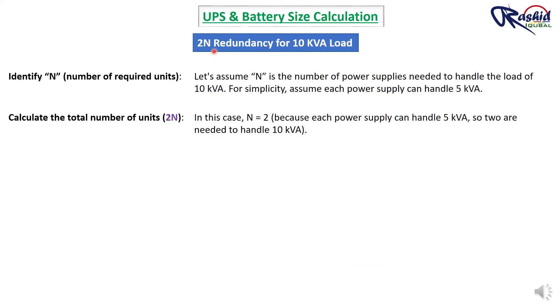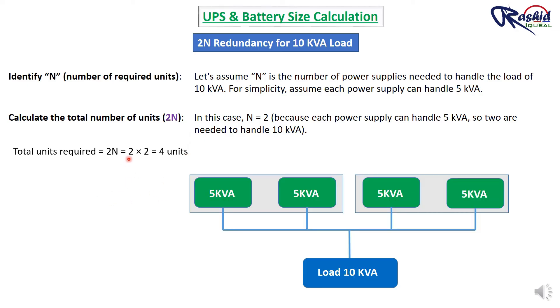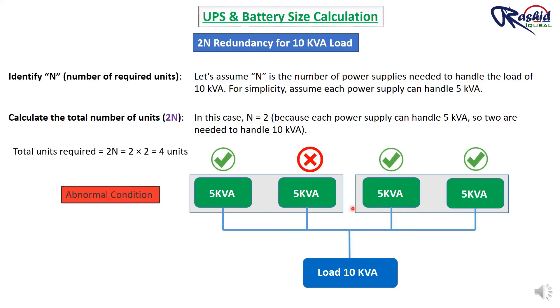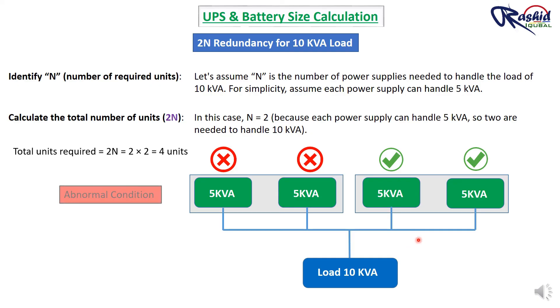For 2N redundancy with a 10 kVA load, we need four 5 kVA UPS units in two complete sets. Both sets are active simultaneously, sharing the load or capable of taking over completely. If one or two UPS units fail, the other two continue supplying power without disruption. Only if three UPS units fail would the single remaining unit be unable to handle the full 10 kVA load.